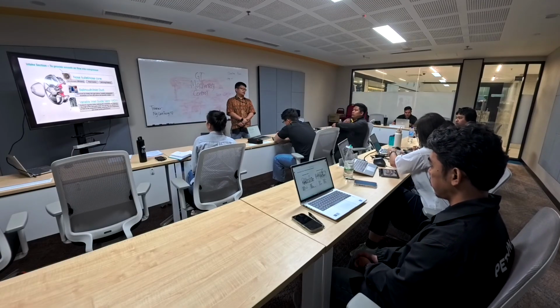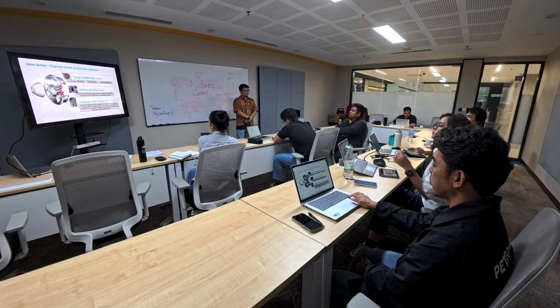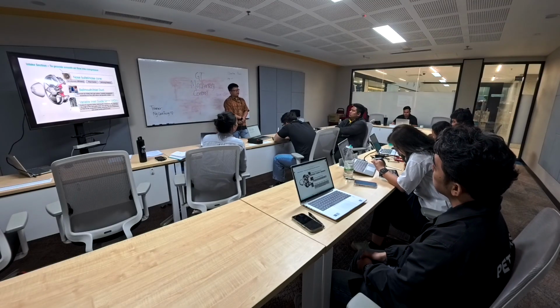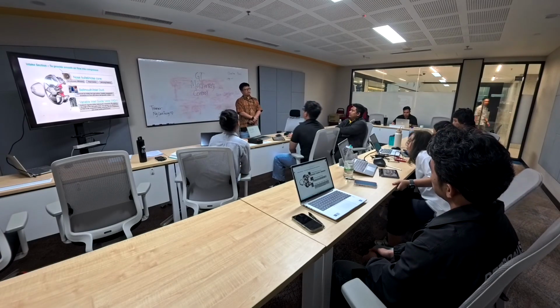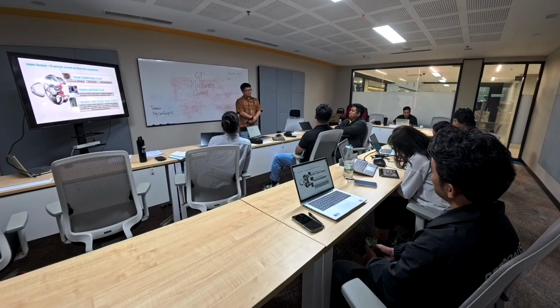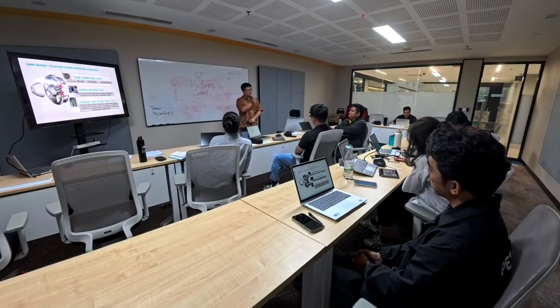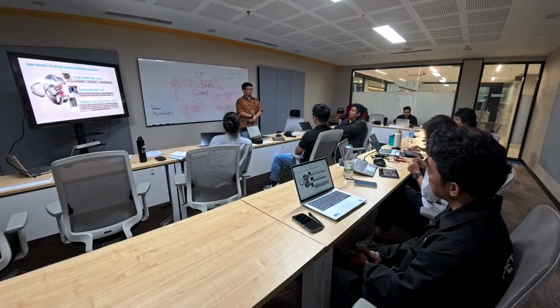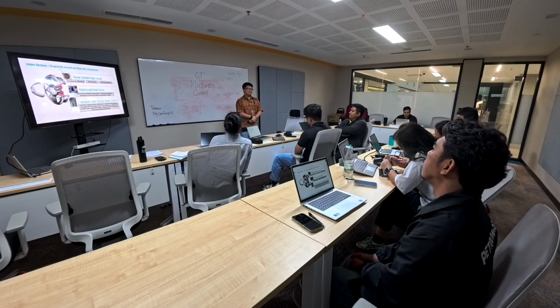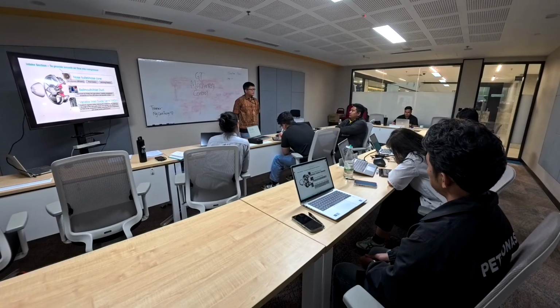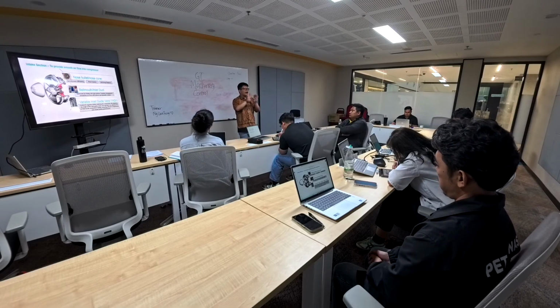During starting up, this VIGV is in a closed position. When we say closed position, it doesn't mean that it's fully closed like a fire damper. It's kept at a very minimum opening degree. If you look at the gas turbine model that you have at your location, mine is a 750. You open the enclosure and look at the IGV or even your engine nameplate. Normally it will state the opening degree. If I'm not mistaken, it normally ranges from 5 to 12, maybe 8 degrees at a fully closed position. That means when we talk about VIGV being closed, it's not totally 100% closed, unlike a fire damper. When a fire damper is closed, it's really closed. No air can escape through.